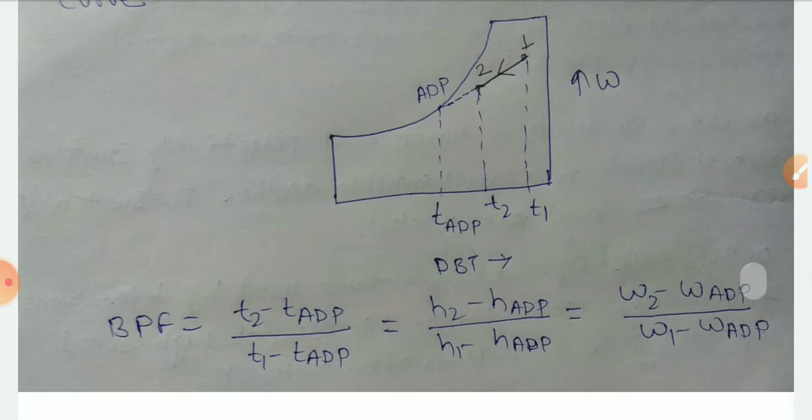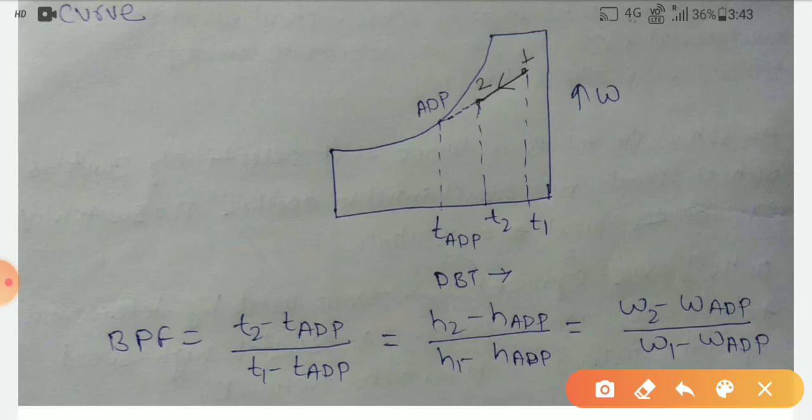So now I am going to write the bypass factor for ADP. I have already explained what bypass factor is. So you can write T2 minus TADP divided by T1 minus TADP. In the same way, you can write it in terms of enthalpy.